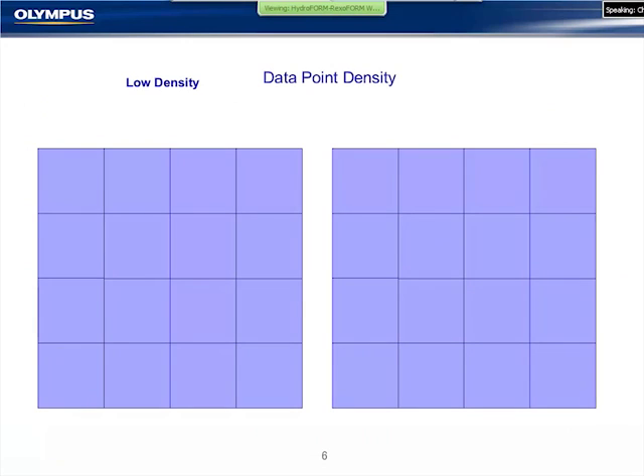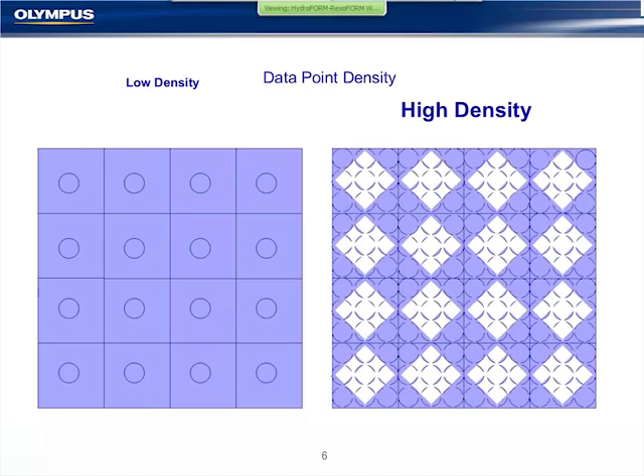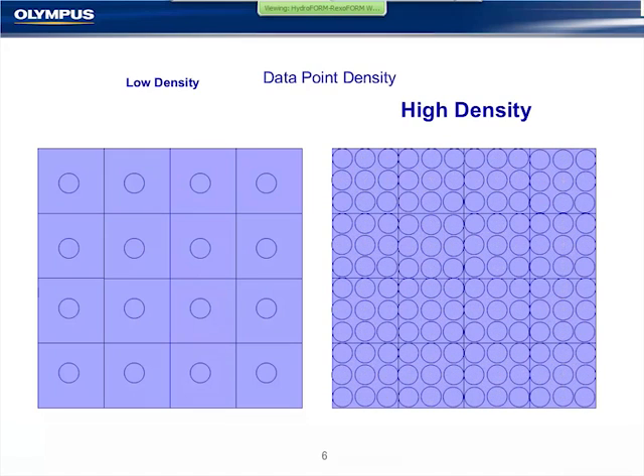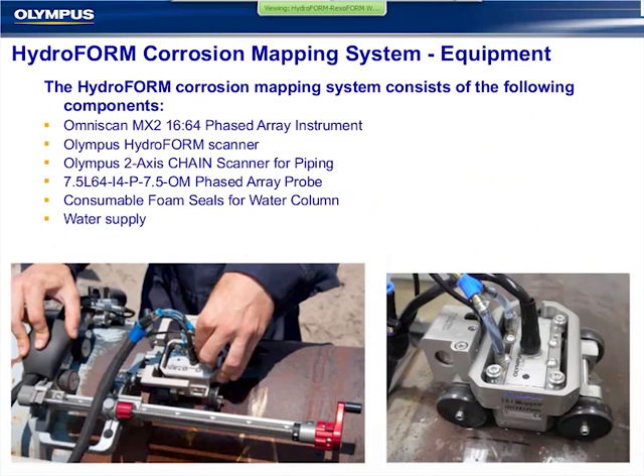And we can see here the low point density, typically 2, 4, or even sometimes 1 millimeter from a conventional raster scanner, compared to the point density that's possible with the phased array probe. One circle essentially equals one A scan, summed together in C scan, B scan, and D scan presentations.